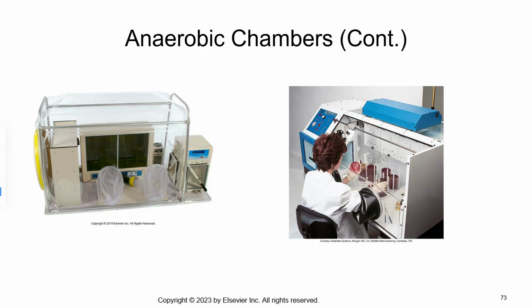So typically when we look at our anaerobes, we will plate them in standard conditions, and after they've grown in those standard conditions, we would want to look at them and see if we have to do any subculturing or any further workup from there. And if we do, we would want to open those up in an anaerobic environment. So what you do is there's a door here. So you would open up the door and you would put the items inside of the door. Then you would press the button and it would exchange out the environment, removing the oxygen.